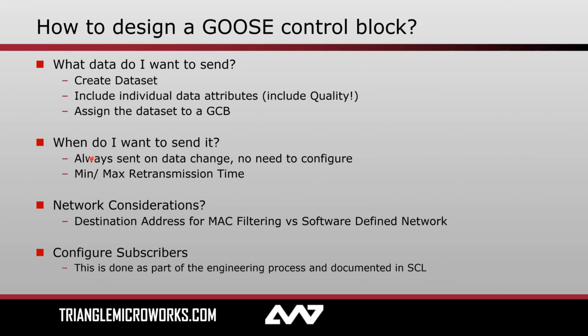So in GOOSE, the data is always sent on change. So we don't have those trigger options that we spoke about before, like data change or cyclic. However, we do still need to keep in mind our min and max. A lower min time is typically reserved for more mission critical functionality. It will result in a higher network load, but there's a higher guarantee of quality of service.